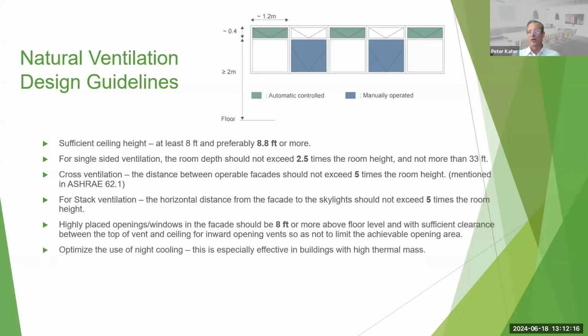Optimize the use of night cooling. This is where the natural ventilation system opens the windows at the coolest time of the day, which is pre-dawn typically. This has the effect of pre-cooling the interior of the building. And that means that the mechanical ventilation system or heating system or cooling system doesn't need to be turned on until later in the day, because you've pre-cooled the building, I should say, just the mechanical cooling system. This is especially effective in buildings with a high thermal mass, which can use that pre-cooling effect for longer during the morning hours of operation or occupancy of the building.